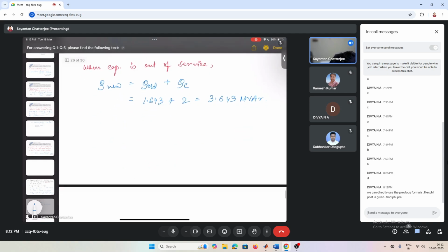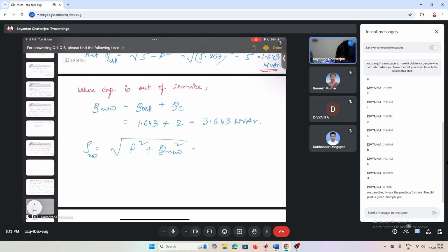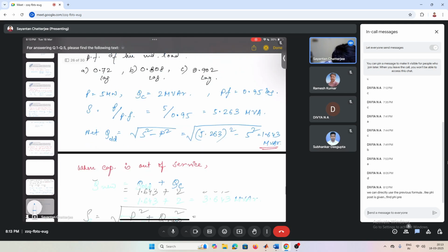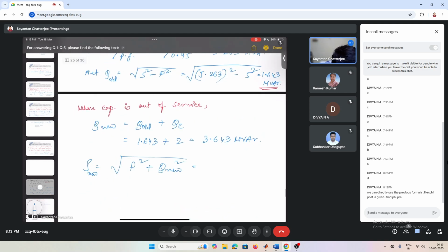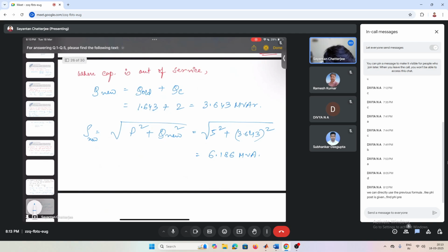So now what we can do, we can calculate S new, which will have P same but Q becomes new. P required is 5 megawatt. So 5 square plus 3.643 whole square, root under, gives answer 6.186 MVA, which is the new MVA.